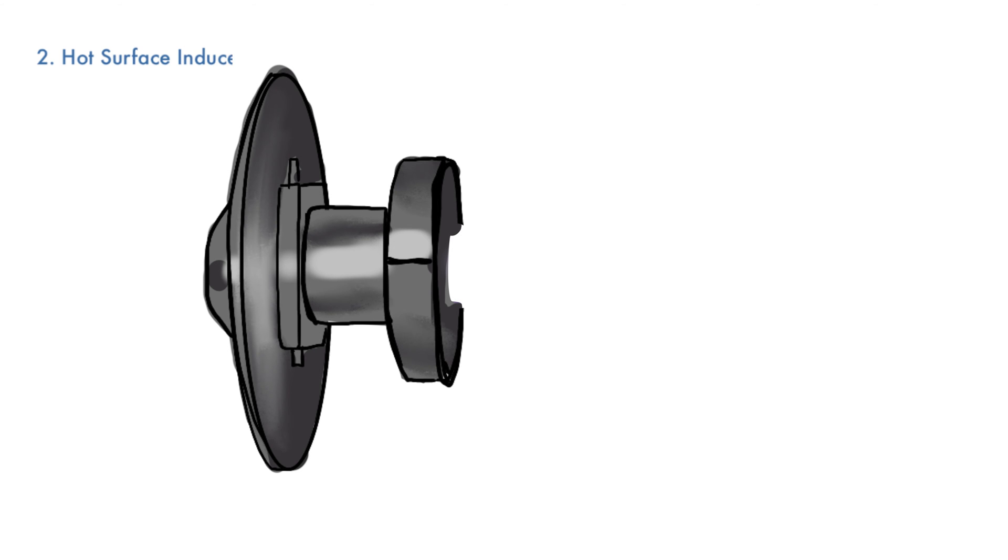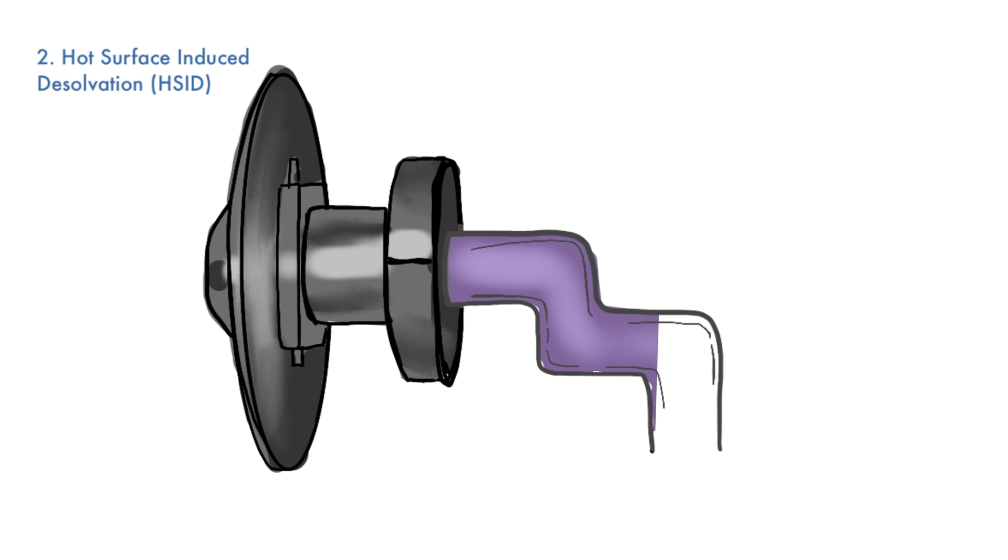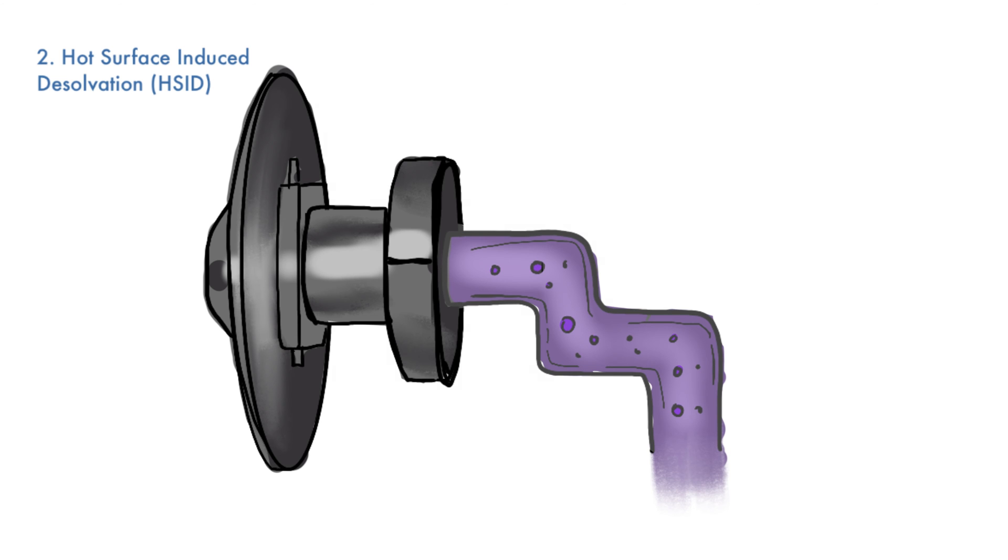From the coaxial flow region, samples pass the hot surface-induced desolvation, HSID, system. The 350-degree heated inner surface and a laminar flow of gas shield ions and solvated species from striking the HSID walls, acting as constant cleaning mechanisms. Additionally, solvated species gain energy from the hot gas and become desolvated. This enables enhanced uniform response across the entire mass range with no lens optimization.